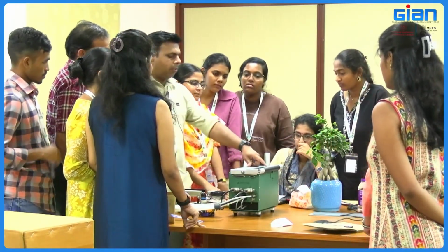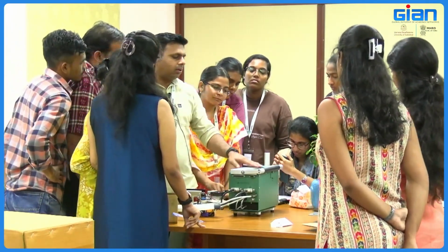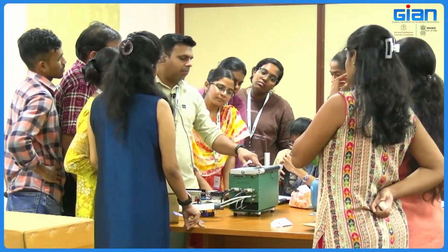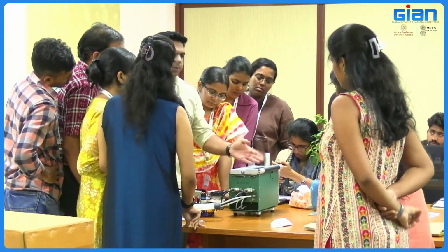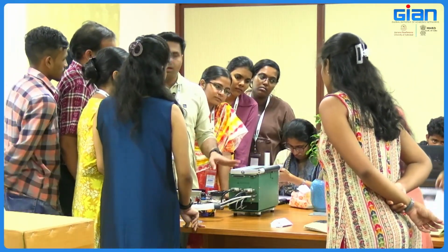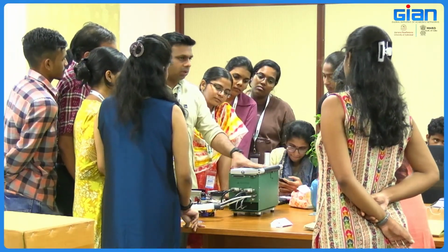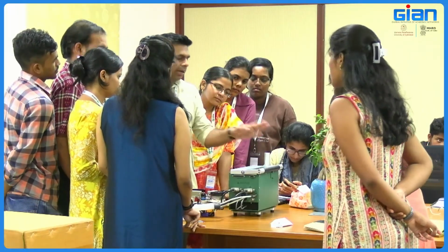So what do we have to do? We have to make this sample 0. Okay. So initially when you wait, these readings will stabilize. It will be minus 5.5, 5.6, 5.7. It will be 9.1, 9.2, 9.3, 9.4, this kind of thing. After that, these values are a bit different, right? Then you have to zero this. Zero this means these two values will come very close to each other.